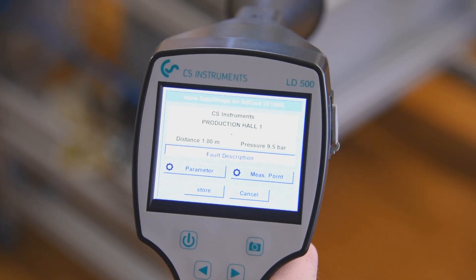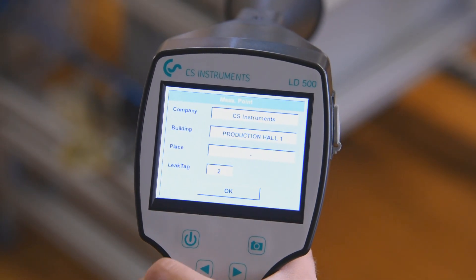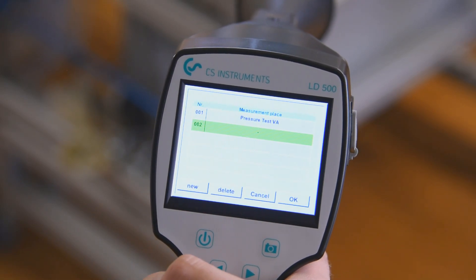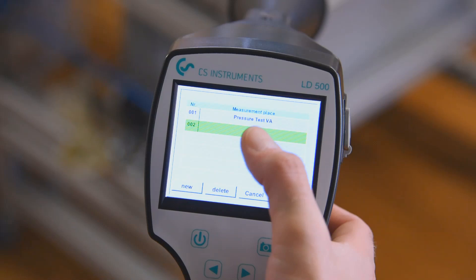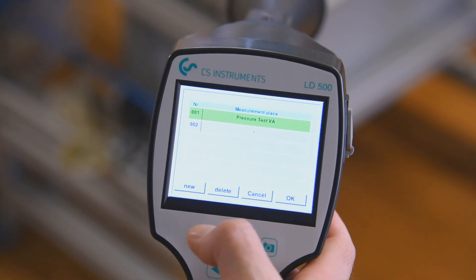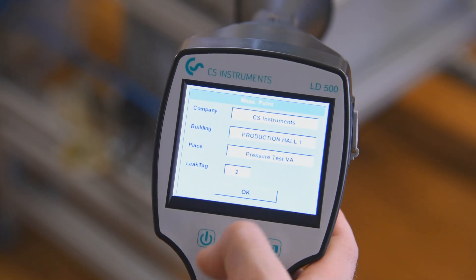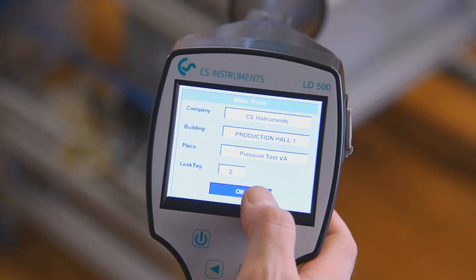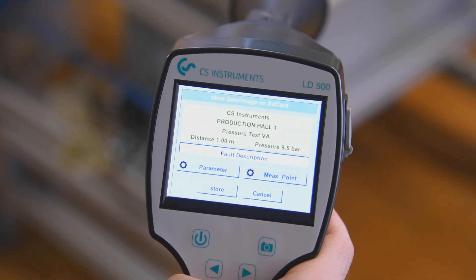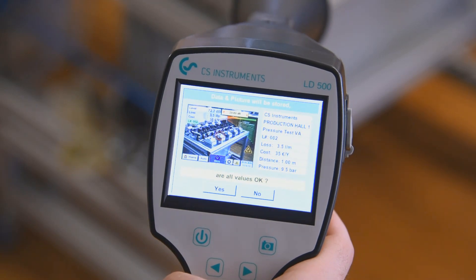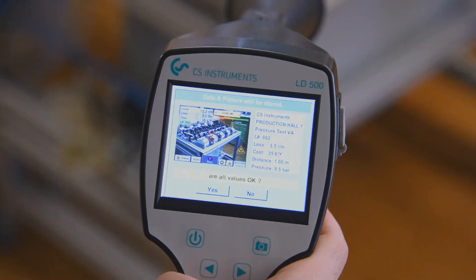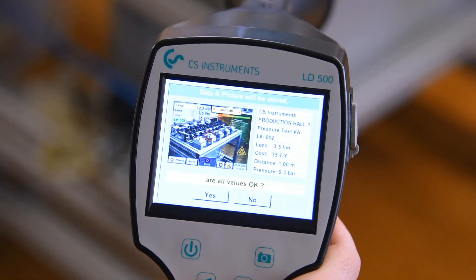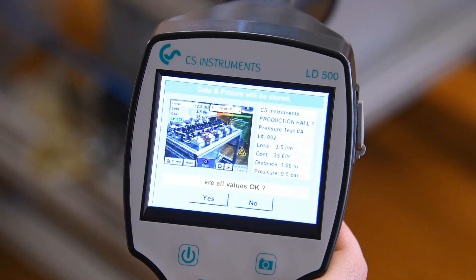After the leak is located, it can be described and catalogued. If necessary, adjustments to the configuration can be carried out for each leak. For example, details describing the leak location like company name, building, and leak location can be adjusted, as well as the important parameters of system pressure and distance to the leak. Even the attached sensor can be changed for each individual leak location. Finally, all parameters can be double-checked for accuracy before storing the leak description.